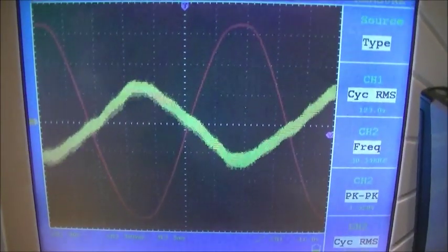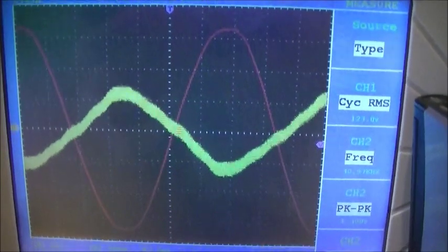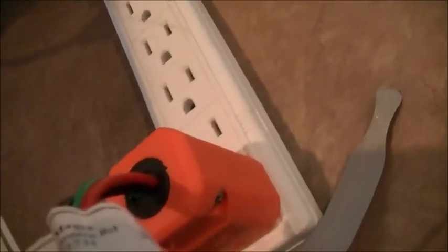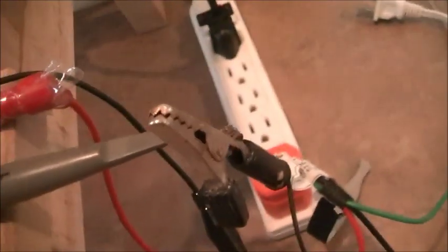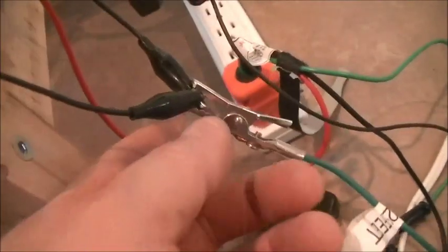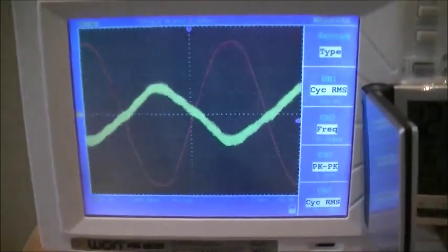We're using a battery powered oscilloscope. As you can see, our battery powered oscilloscope has two waveforms on it. The yellow is the sidewalk voltage, and the red is the 120 volts AC waveform. Our probe connections are here, and if we follow them down, we find that the red probe is connected into the 120 volts on this power strip. The yellow probe is connected into this very long lead that goes out to the sidewalk. Our common connection for both probes connects into a non-electrified eight foot ground rod in my back garden to give us the reference voltage. And that's the resulting waveform.